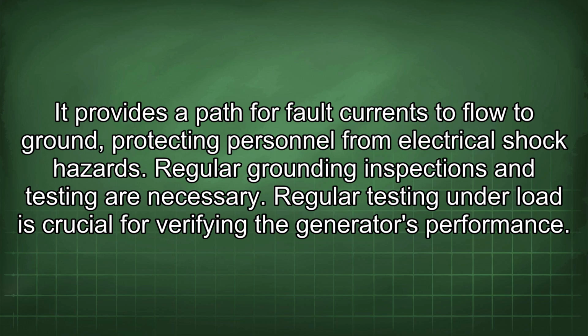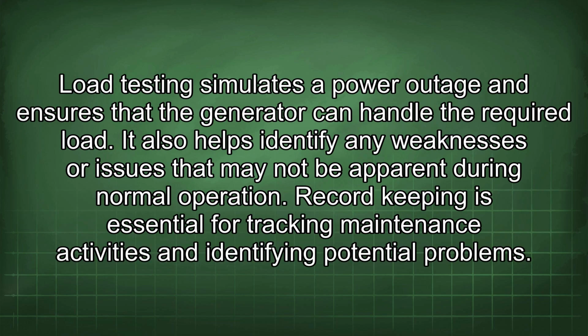Regular testing under load is crucial for verifying the generator's performance. Load testing simulates a power outage and ensures that the generator can handle the required load. It also helps identify any weaknesses or issues that may not be apparent during normal operation.